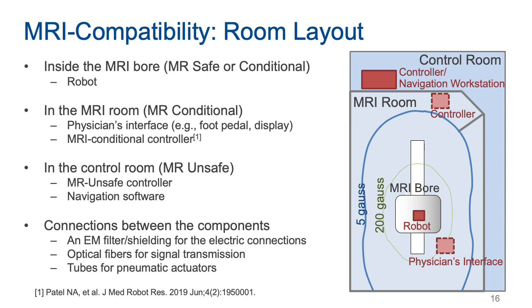Because we often have multiple components with different classes of MR safety in the system, it is important to consider how those components are placed in the MRI environment. The robot must be placed inside the MRI bore because that is how the device is used. The robot can be either MR safe or MR conditional. There are other components that need to be inside the MRI room, such as the physician's interface like foot pedals, switches, and a display. In some systems, the robot controller is designated as an MR conditional device and can be placed in the MRI room, maybe outside a specific Gauss line, depending on the condition. And of course, there are MR unsafe components in the system, such as a regular robot controller and a navigation workstation. Those components must be placed outside of the MRI room and properly labeled so that no one will move these devices into the MRI room.